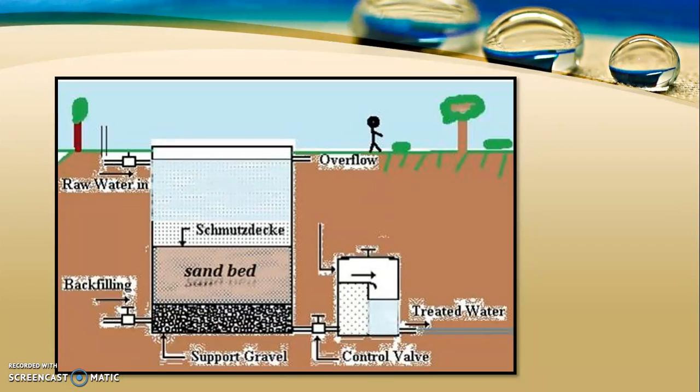To clean a slow sand filter, the entire top sand layer must be scraped out, washed, cleaned, dried, and replaced — requiring significant manual labor. Operation and maintenance problems and clogging of pores are major issues with slow sand filters. To avoid these problems, rapid sand filters are nowadays used for filtration in water treatment plants.